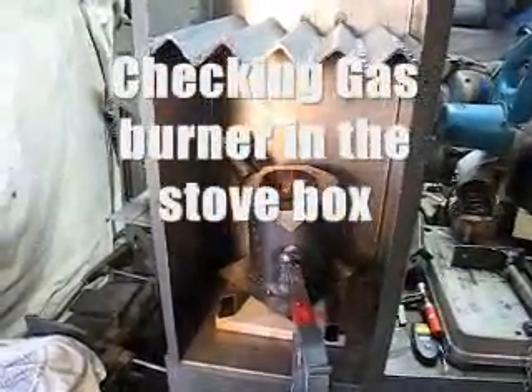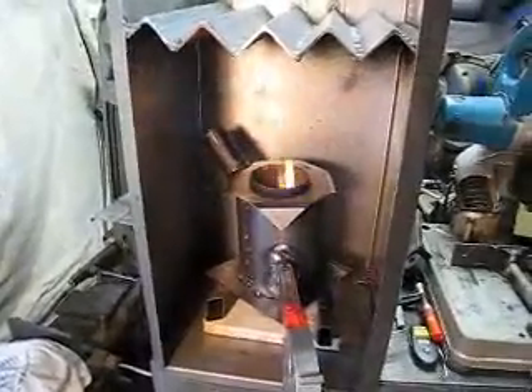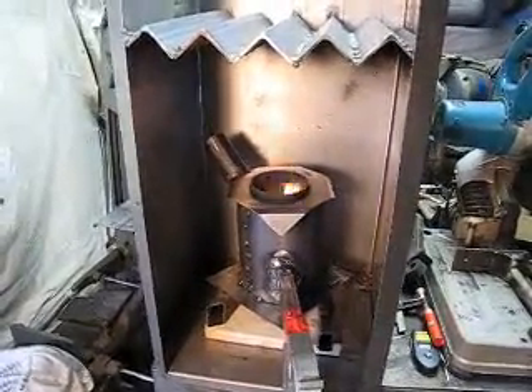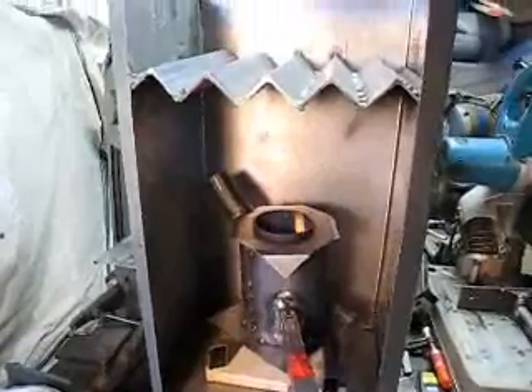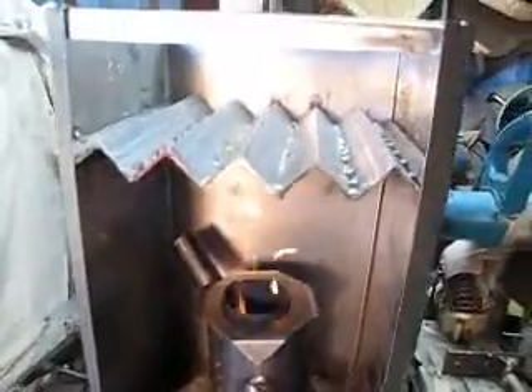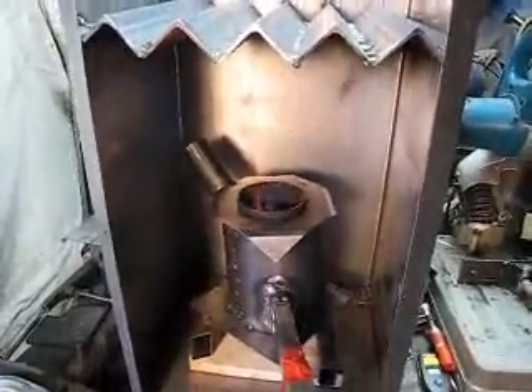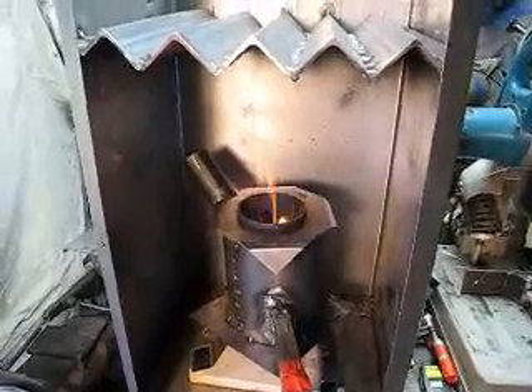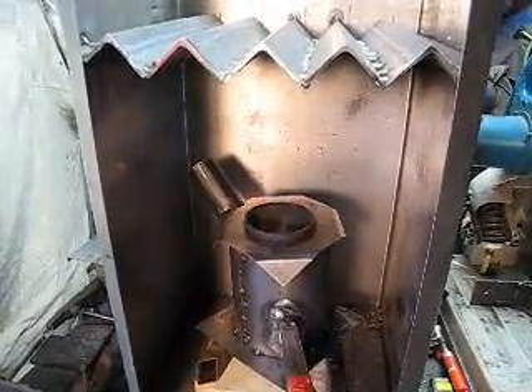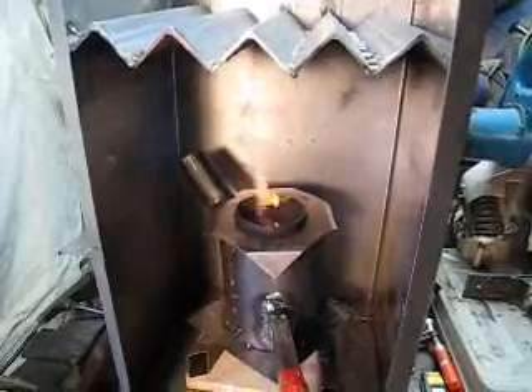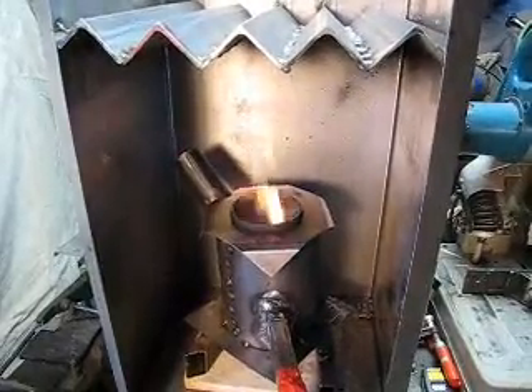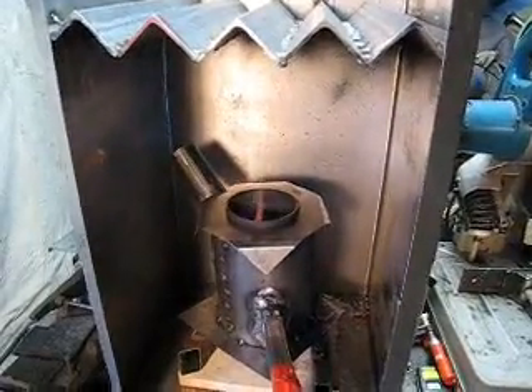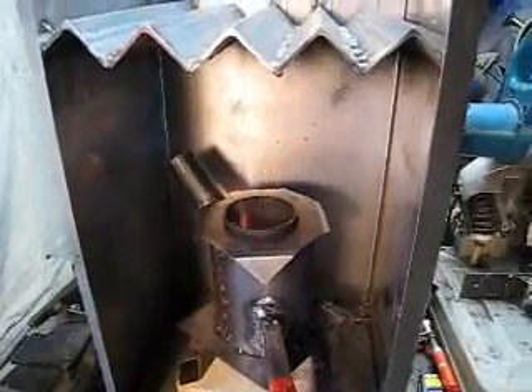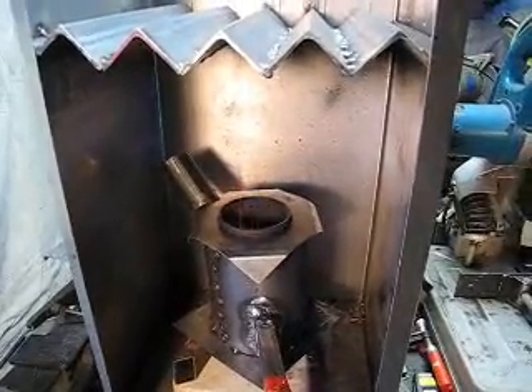Well, the next step in the process is to measure the amount of heat that's hitting the top of the heat exchanger, which is right up here. We have a laser temperature sensor that we can point, and it'll automatically give us the temperature. Right now we're just starting the pellets up. We haven't got the combustion fan going, but once it gets up to that temperature, we'll kick the fan on and do some measurements.